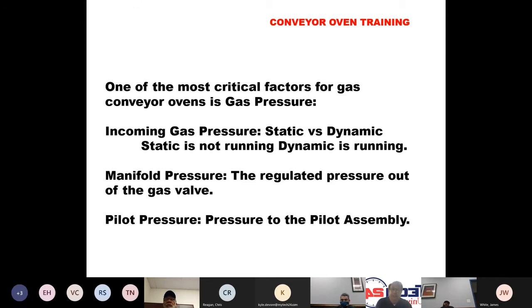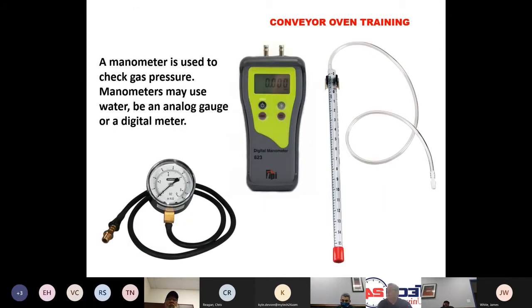The last gas pressure adjustment is pilot pressure. This varies from manufacturer to manufacturer, but typically your pilot pressure is a little bit higher than manifold pressure. If I have an oven that's running 3.5 inches of manifold pressure, I will run about 4 inches of water column on my pilot. That too can be adjusted depending on how your flame current is reacting. If you have too low of pressure, you'll tend to have ignition lockout issues. If you have too much pressure, you may have a situation where your burner doesn't ignite because the module never sees the flame current. Just a little bit over what your manifold is typically.